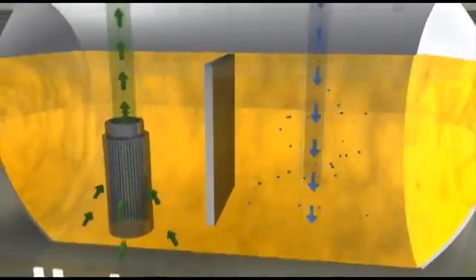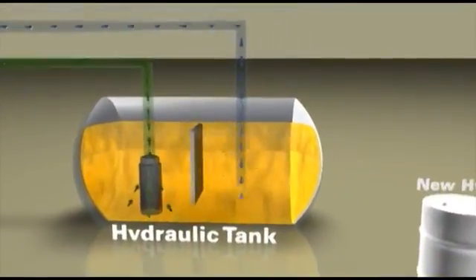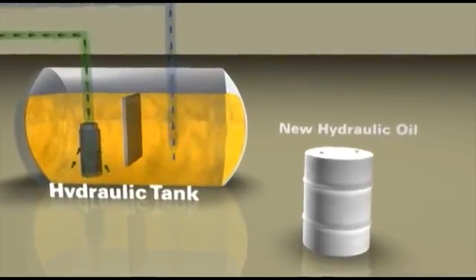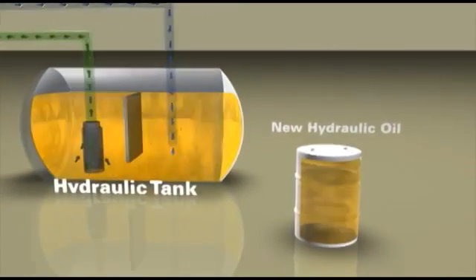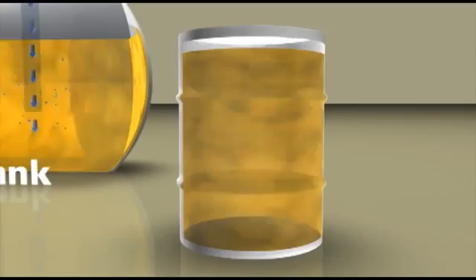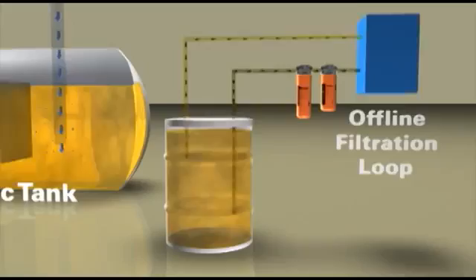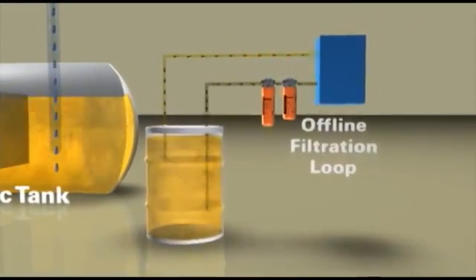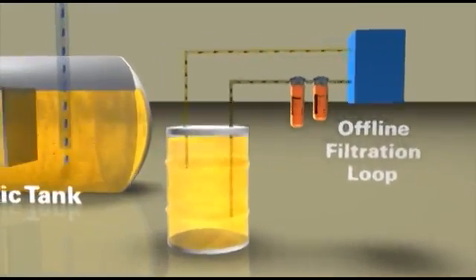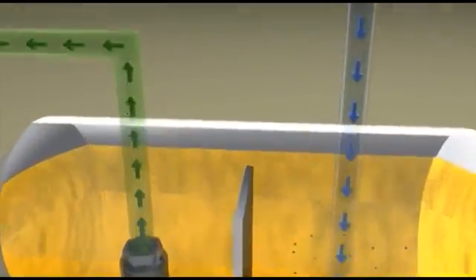Let's look into the hydraulic oil holding tank. It's here that most of the contaminant finds its way into the oil. First, it's important to note that new hydraulic oil is not pure. At an approximate ISO cleanliness level of 21/19, it is significantly higher — that is, less clean — than OEM standards. This has prompted a leading global heavy equipment manufacturer to recommend filtering new oil before pouring it into the hydraulic tank. Water can also enter the hydraulic system via the holding tank when moist air inside the tank condenses as the outside air cools.